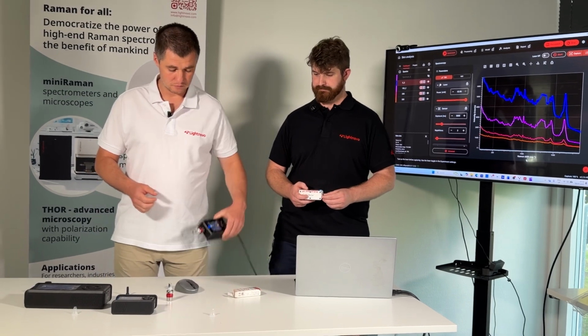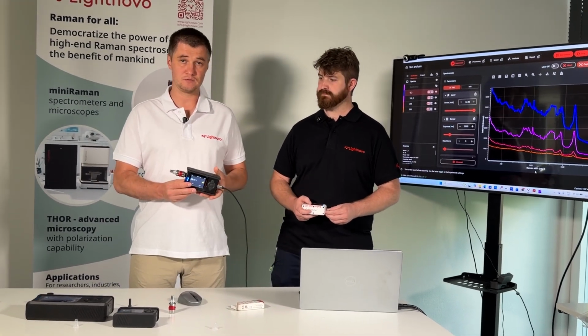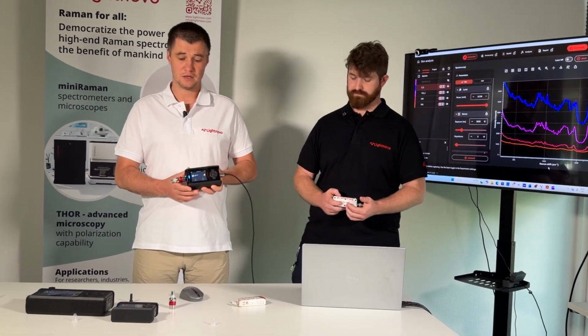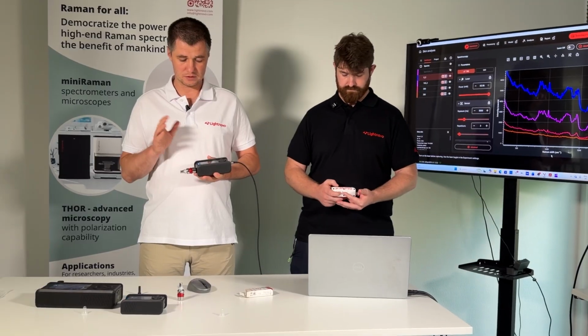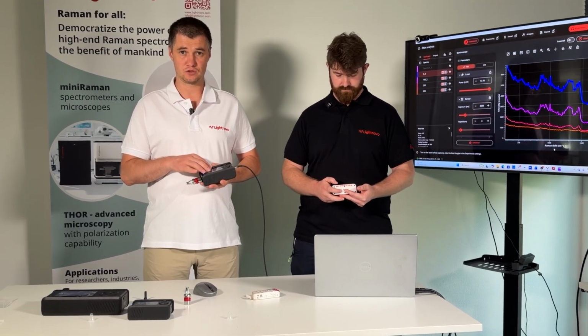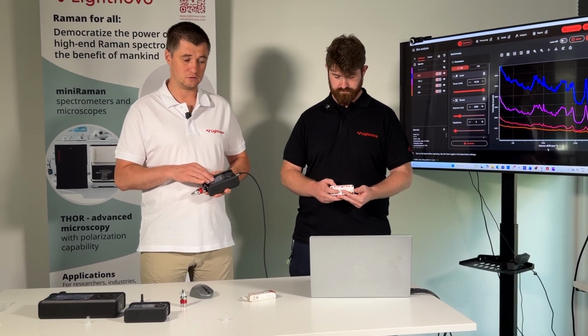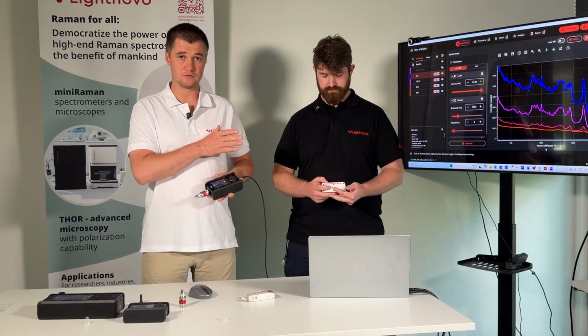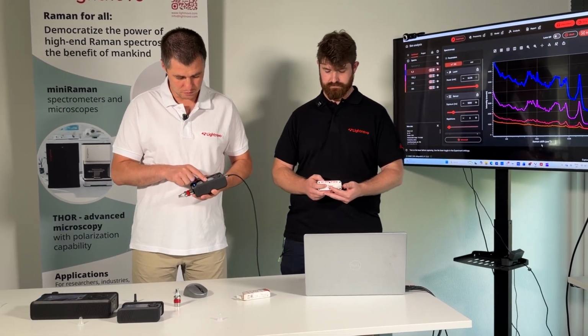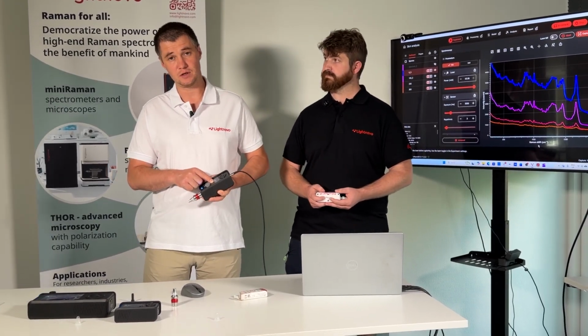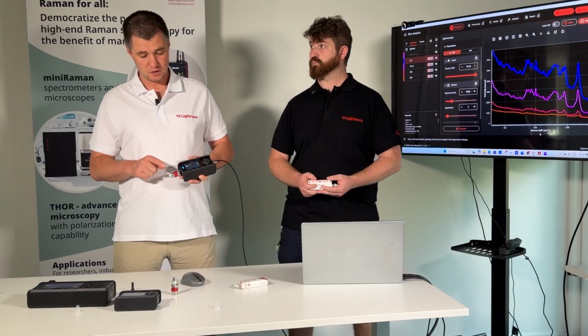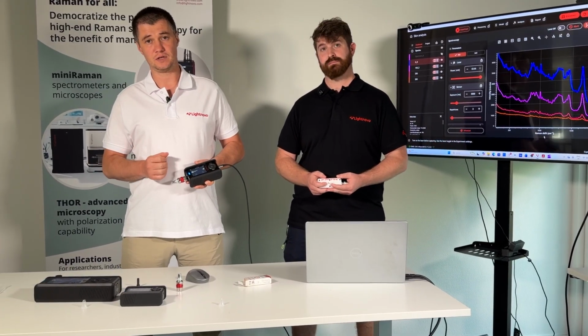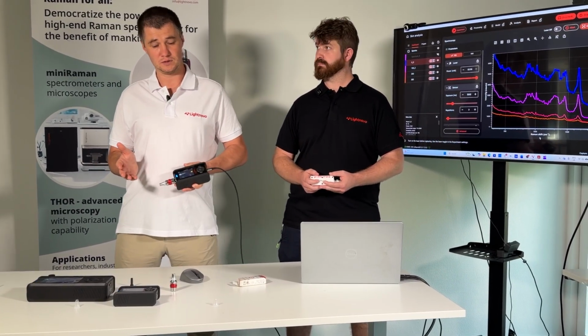But this one, where we demonstrated confocality, it was a single mode laser, and you don't need as much power to reach as good a signal. You saw signal was also very good with this laser, but here power is set to 63 milliwatt, but that is without the probe. After this probe, you will get maybe approximately 40 milliwatt on a sample.